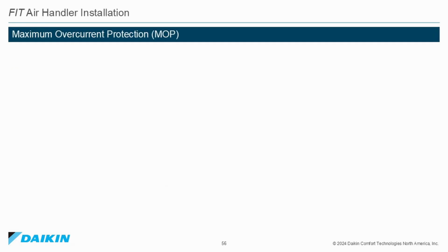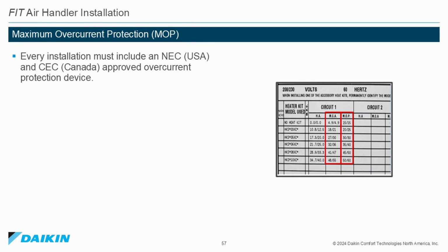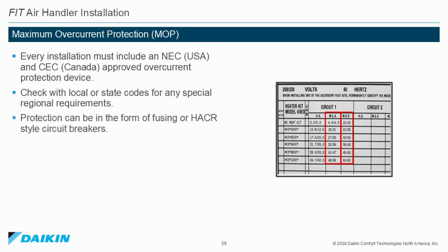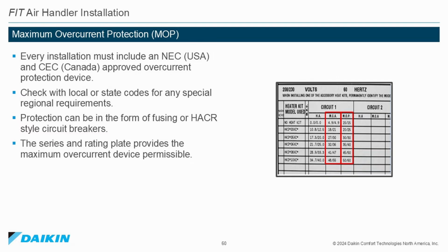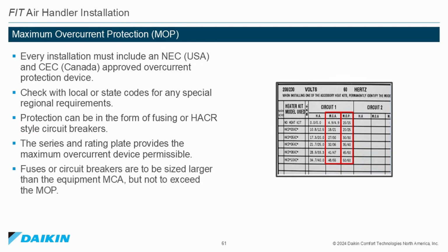Maximum overcurrent protection. Every installation must include an NEC USA or CEC in Canada approved overcurrent protection device. Check with local or state codes for any special regional requirements. Protection can be in the form of a fuse or HACR-style circuit breakers. The series and rating plate provides the maximum overcurrent protection permissible. Fuses or circuit breakers are to be sized larger than the equipment maximum circuit ampacity, but not to exceed the maximum overcurrent protection.